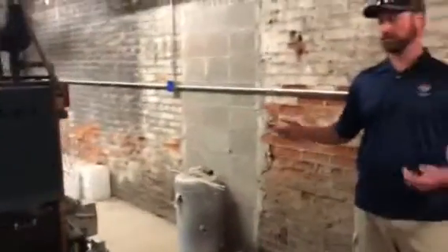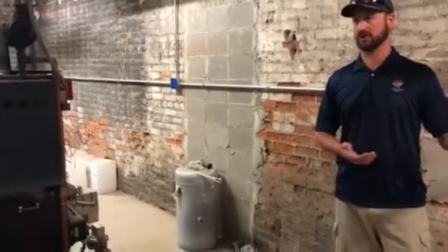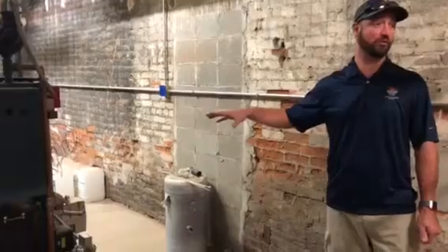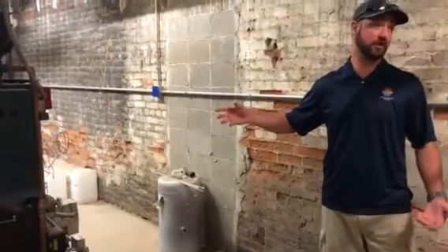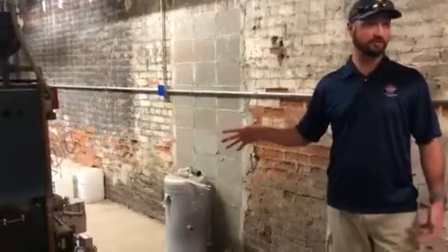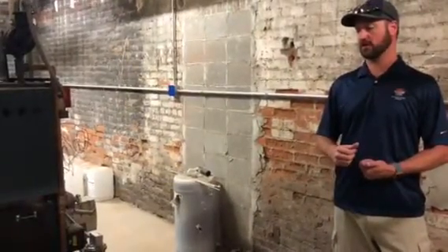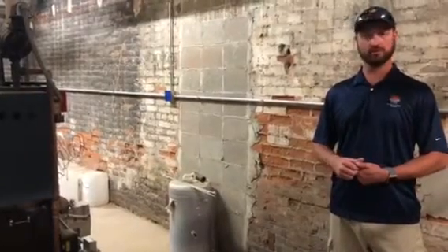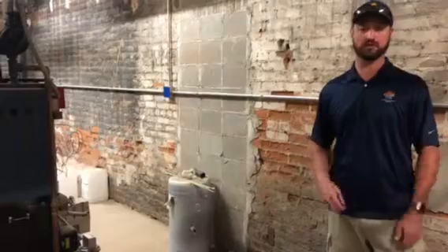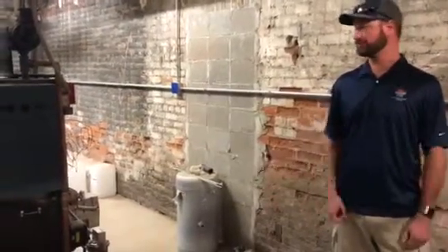One reason that's important is because we are now resetting the boiler temperature based on outside air. So the warmer it is outside, the lower we can run the boilers. They don't need as much heat. So there's cost savings there as well. We also have the ability to shut the boilers off in the summer. We're turning the boilers off June 1st through August 31st. We can adjust that. It gets kind of chilly up here at night, even in the summer, but we have full control.